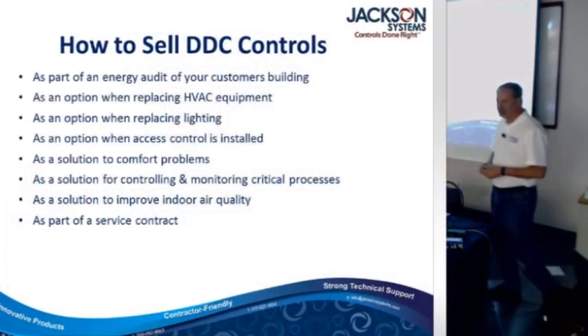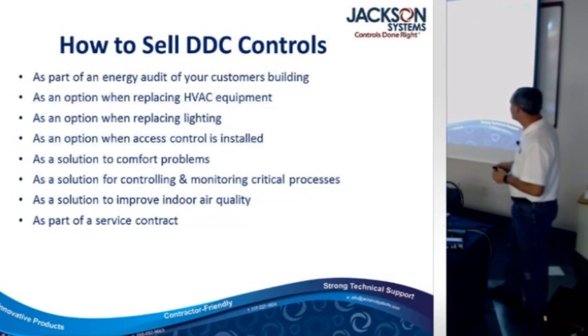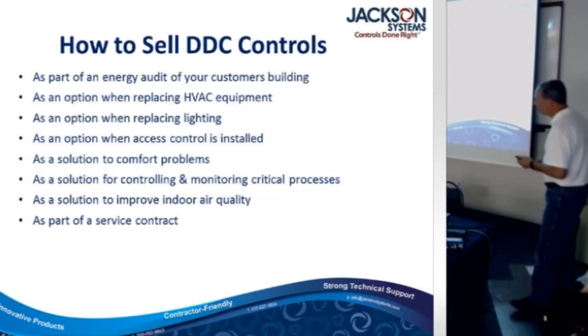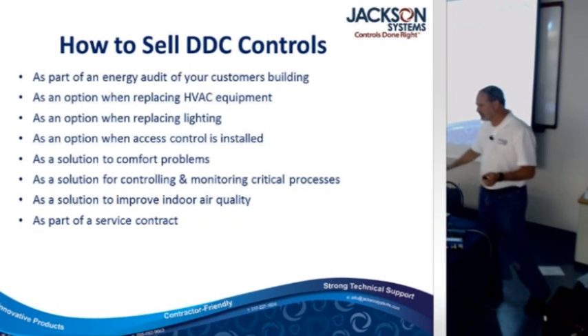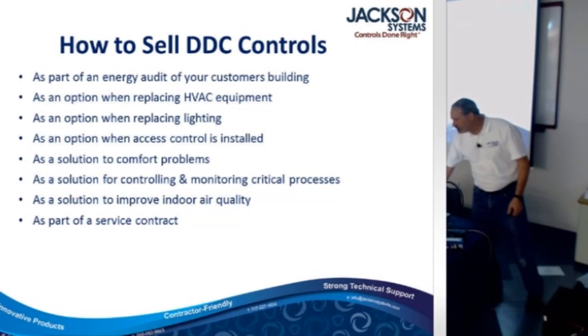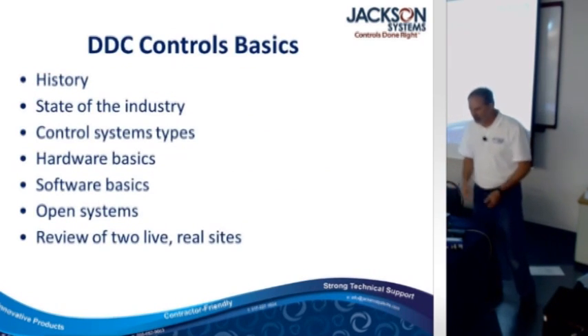and making 74-degree air. Or does it show that it's offline? Maybe you want to have the custodian go check the breakers, make sure the breaker's on. Maybe you can save the customer and yourself some time and money if you have DDC controls that you can monitor from off-site when you have a service contract. Any questions about when or why or how to sell DDC controls? Now I promise we won't talk any more about selling.